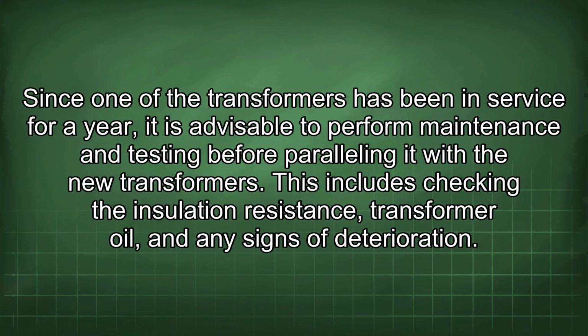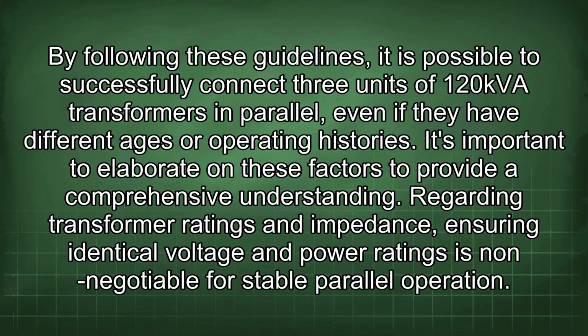Since one of the transformers has been in service for a year, it is advisable to perform maintenance and testing before paralleling it with the new transformers. This includes checking the insulation resistance, transformer oil, and any signs of deterioration. By following these guidelines, it is possible to successfully connect three units of 120kVA transformers in parallel, even if they have different ages or operating histories. It's important to elaborate on these factors to provide a comprehensive understanding.